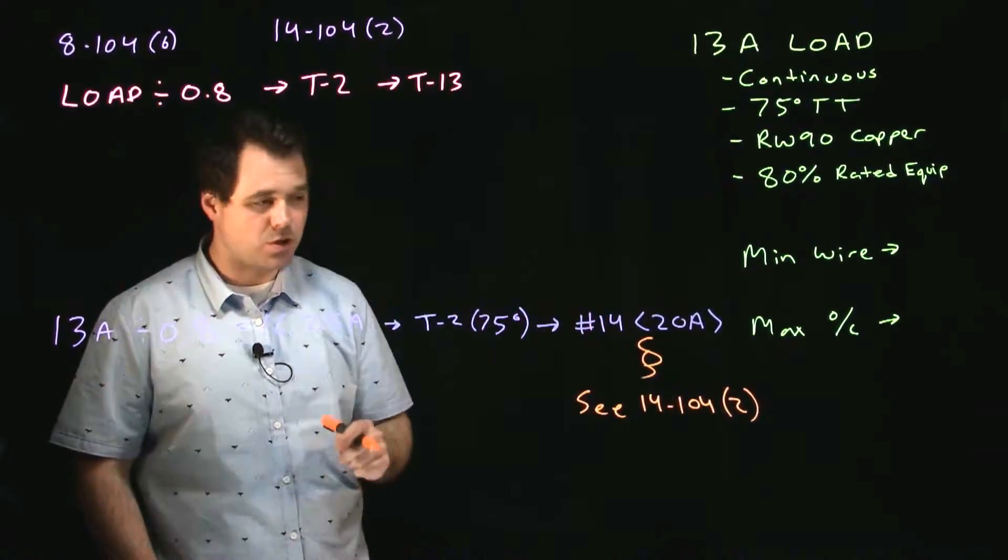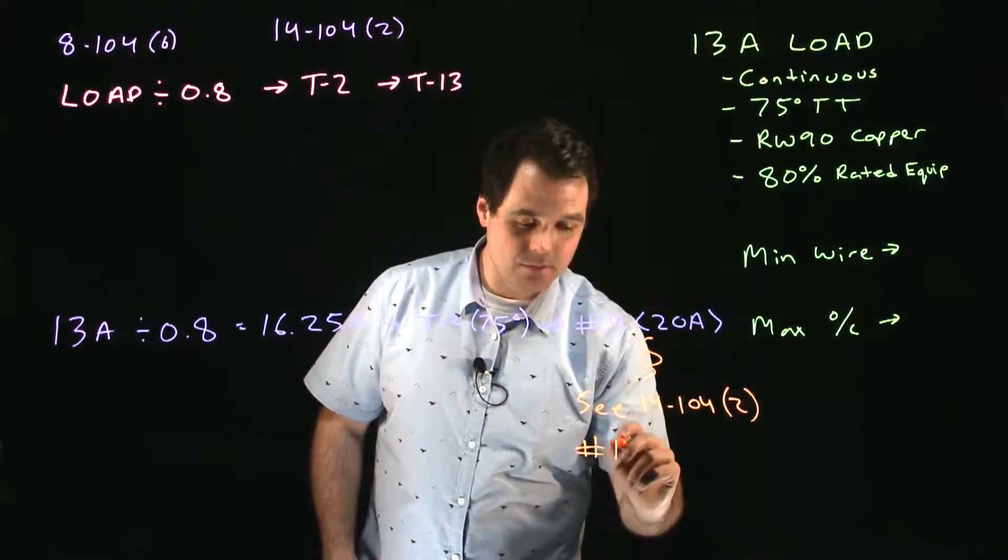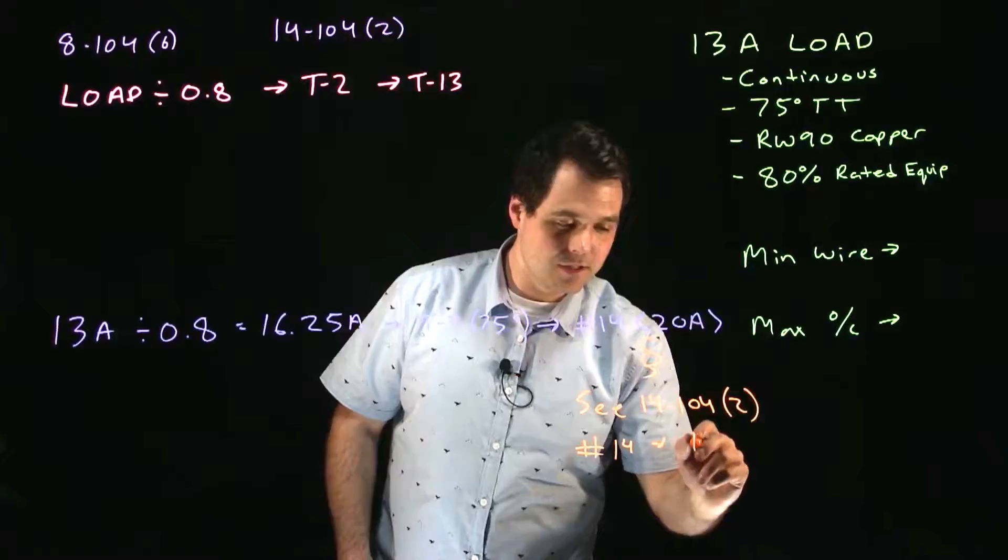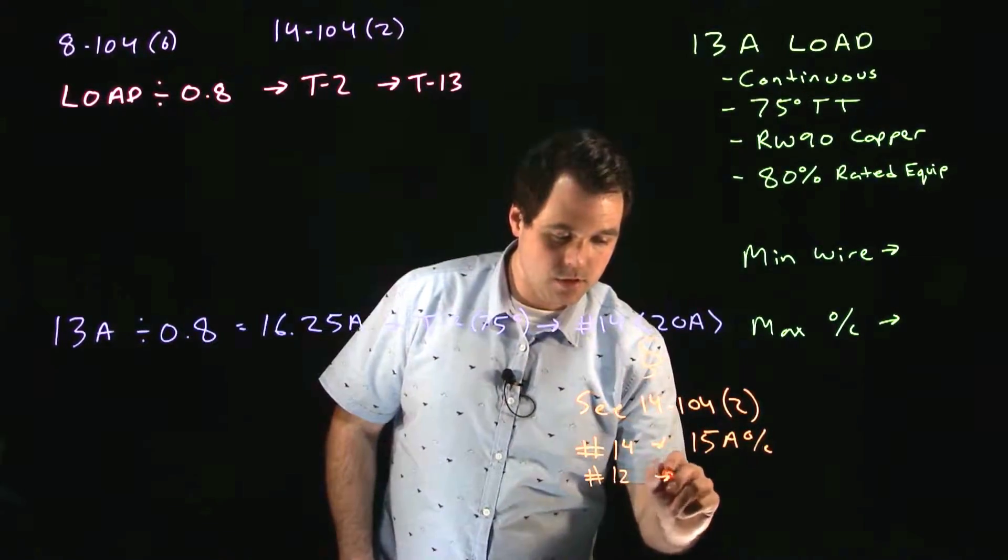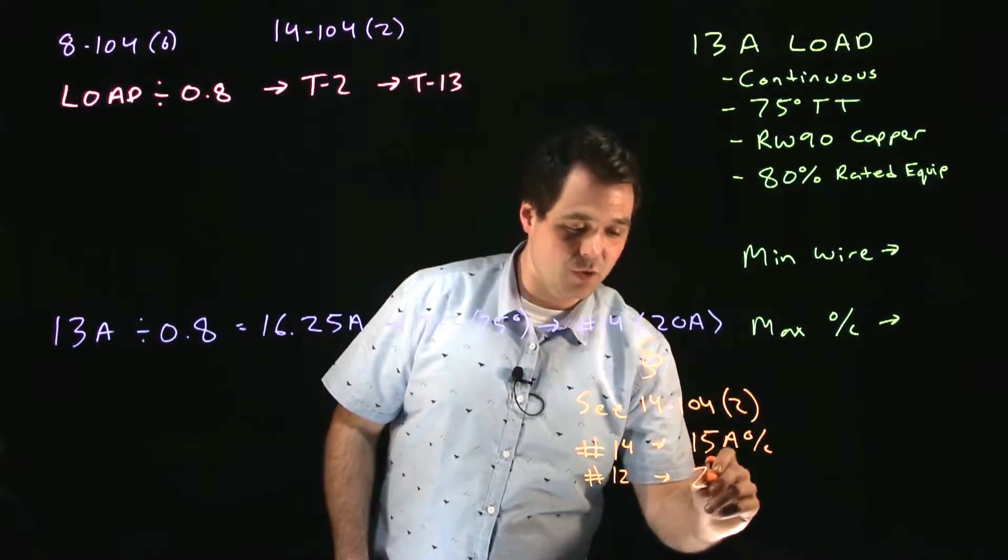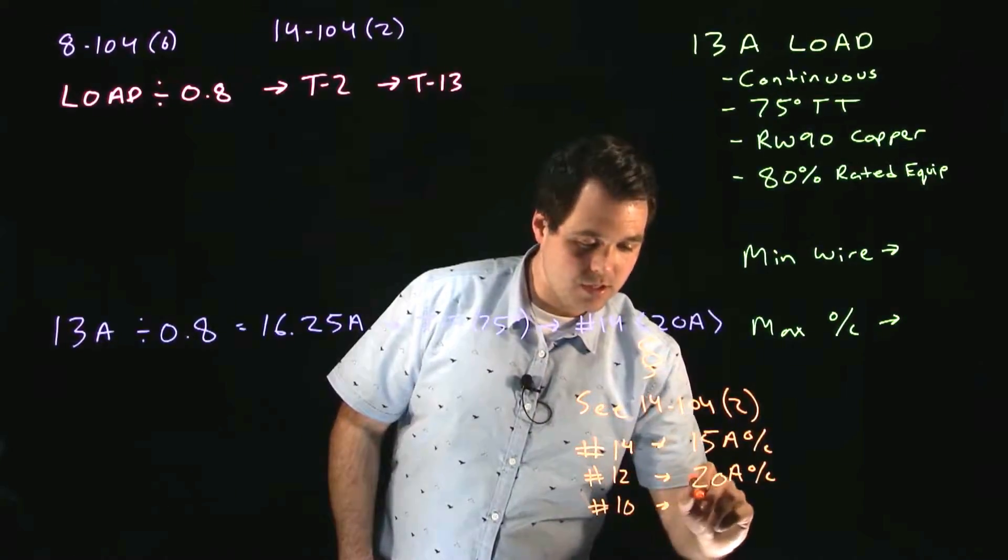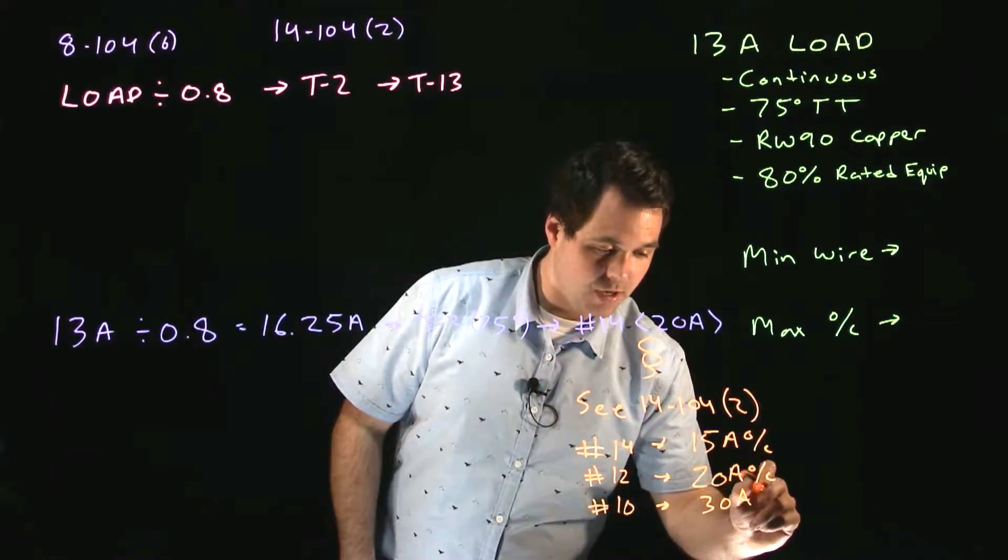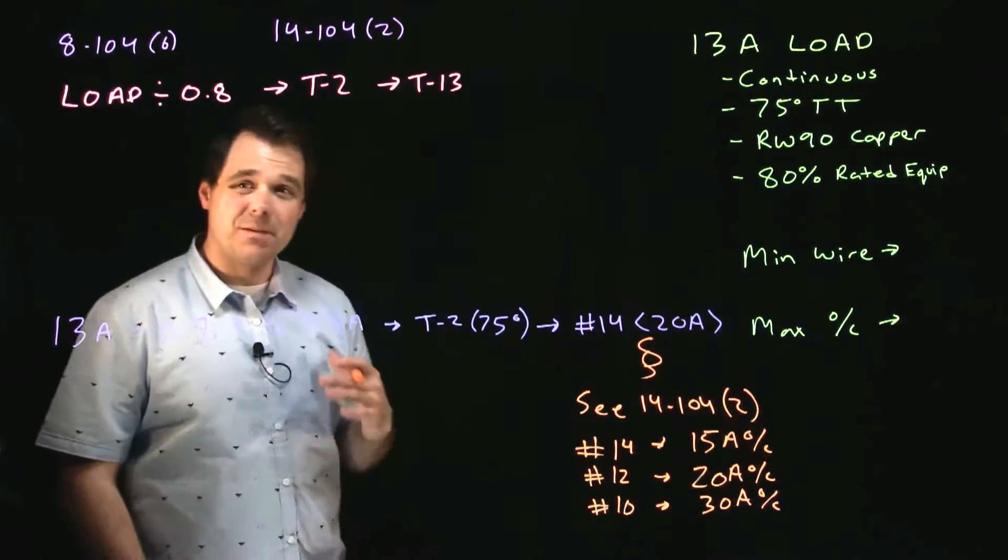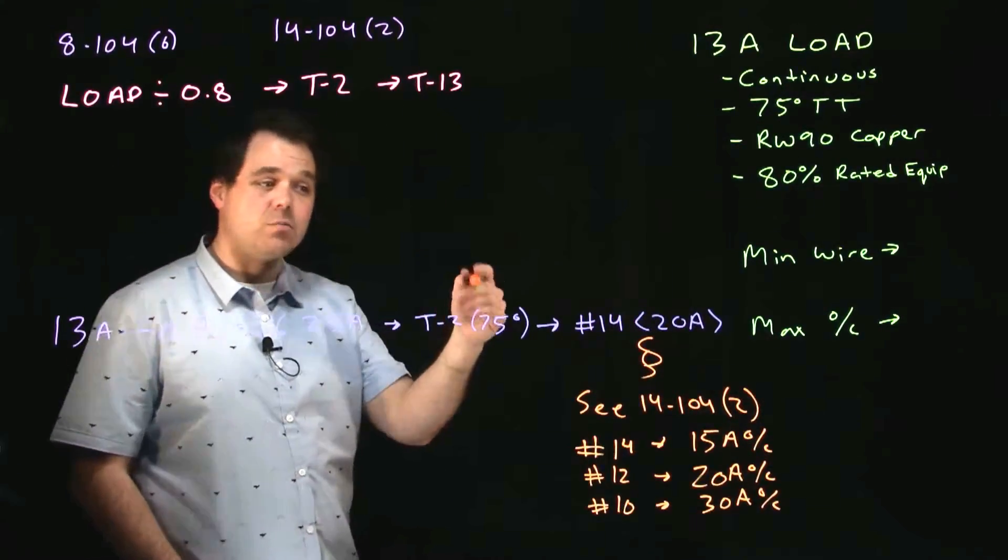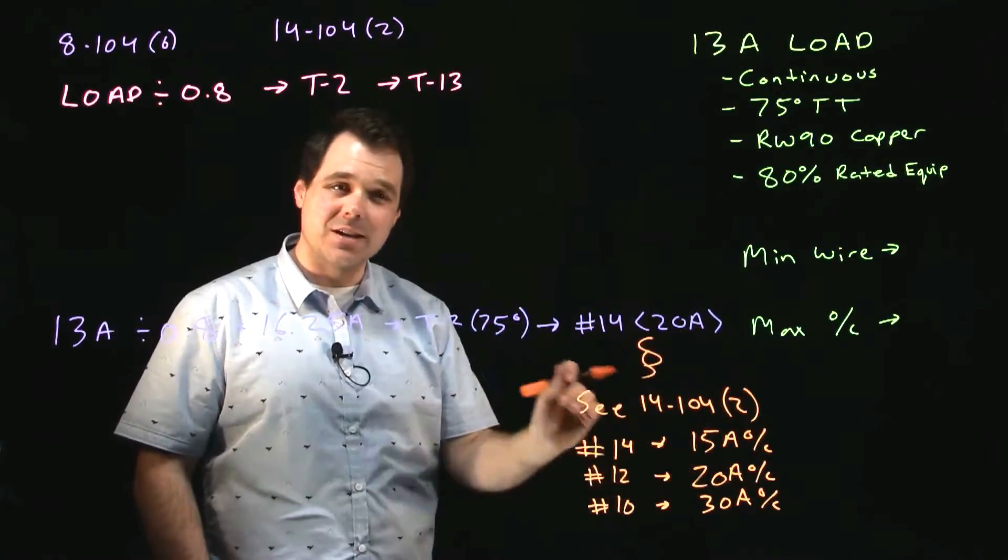So we make our way to 14-104 sub rule 2 says if you have a number 14 wire the maximum OC that you can have on that wire is a 15 amp OC. It says if you have a number 12 the biggest OC you can have is a 20 amp OC and if you have a number 10 the biggest OC you can have would be a 30 amp overcurrent. Those are the maximum allowable overcurrents as permitted by code. So we have to keep those in mind whenever we're on table two: 14, 12, and 10.